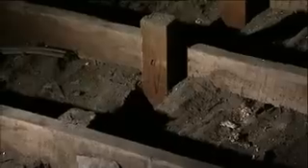Well, there's nothing up here apart from a lot of dust. And no insulation means that Alan and Shirley are losing 25% of their heat straight through the roof. The government recommends that you use about 270 millimetres of insulation in a loft. And these days, most people are using about 300 in a new build. I reckon we should go with that.